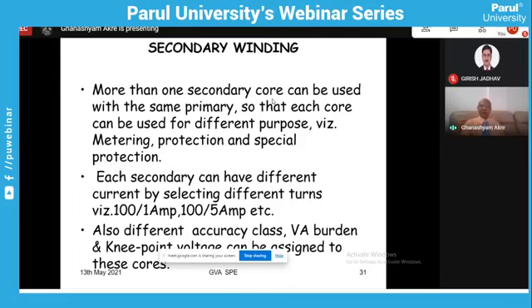For protection, they will be supplying different classes of protection: differential, balance, overload, and all sorts of things, and they will have different characteristics. They will also have one or two cores for metering and tariff metering and for the measurement of the total system. So that is how the secondaries are actually not one only, it can be having two.